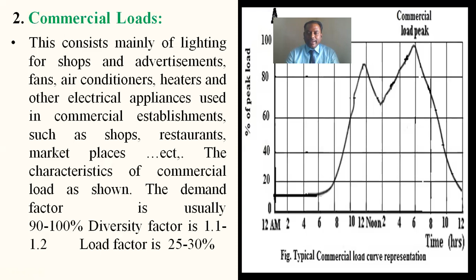So you observe the load curve for a day, how it varies over the 24 hours. This representation is the typical commercial load curve. You observe the peak timings. The demand factor is usually very high, 90 to 100%. If power is not there, the business is very dull, so that's why the demand is very essential. It depends upon the electricity board, and simultaneously they make their own arrangements like generators. The diversity factor is 1.1 to 1.2, and the load factor is 25 to 30%. And the next one is the agricultural loads.